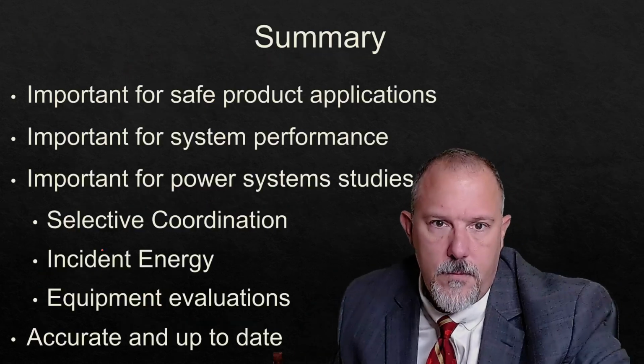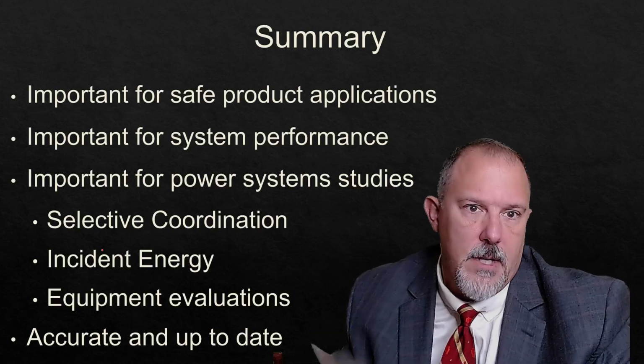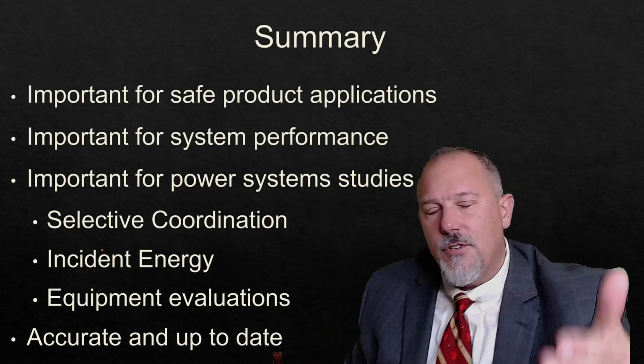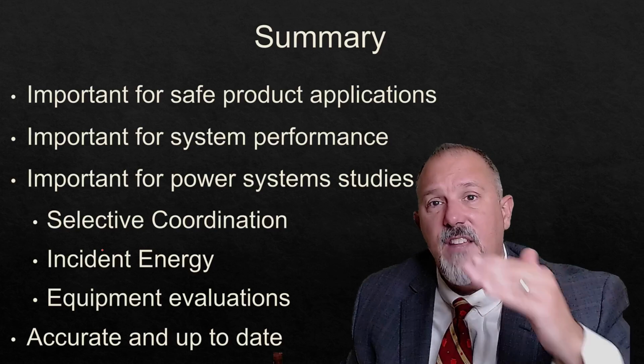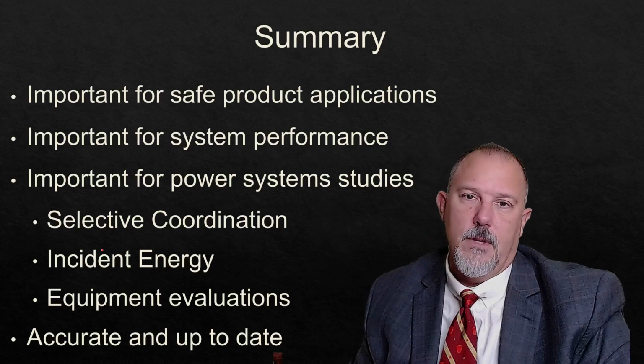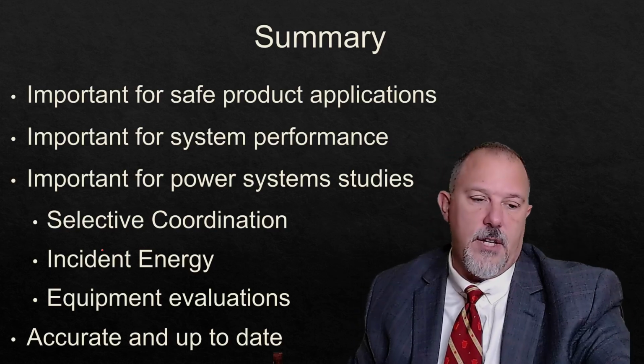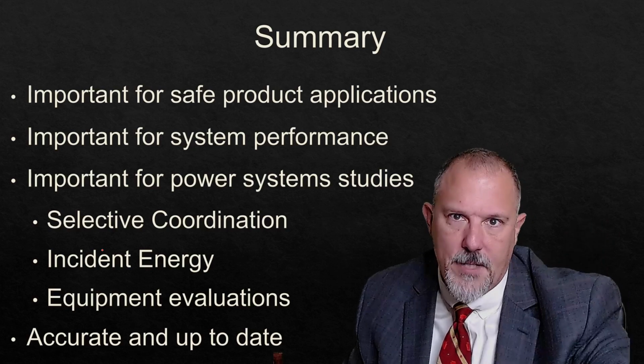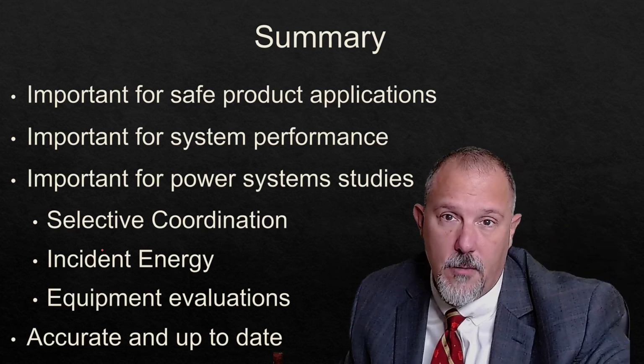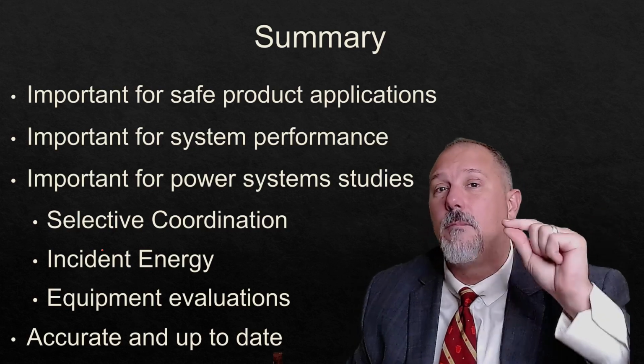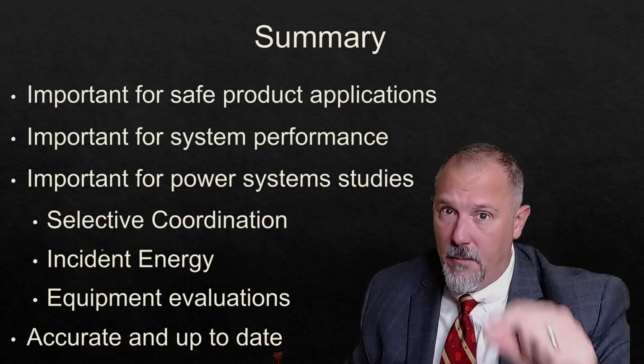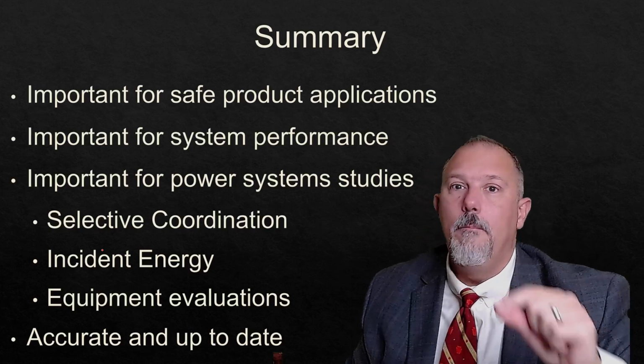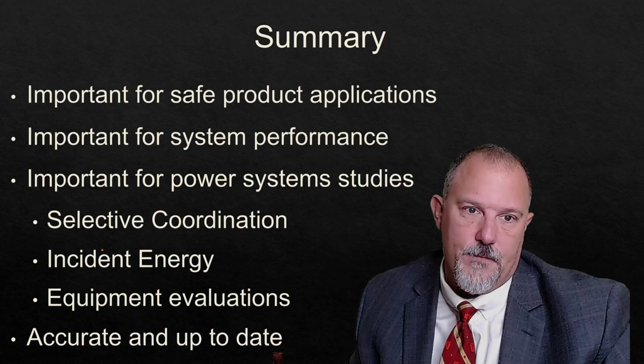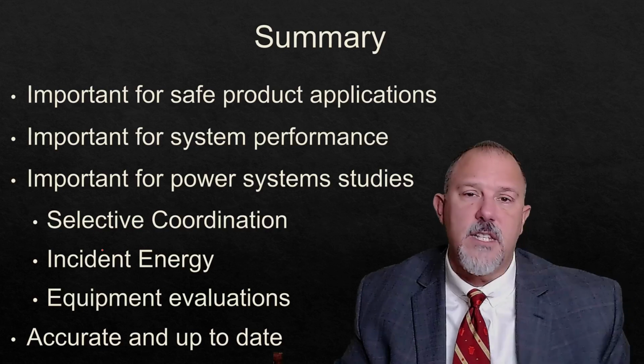So, in summary, you need to know your fault current values because it's important for the safe product application. You need to compare. The code tells us you need to make sure you have the right interrupting ratings, you have the right short circuit current ratings. The code tells you you even have to mark in some cases the available fault current on equipment or make it available through documentation. It's important for the system performance.